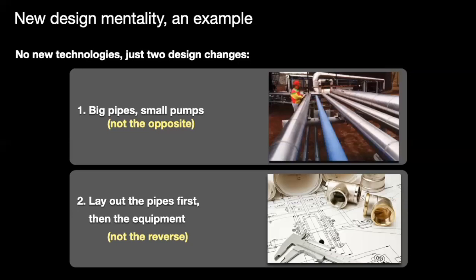But by then, A and B are far apart. Other stuff got in between. They're at the wrong height. They face the wrong way. And by the time the pipe snakes its way across the space, all neatly dressed at right angles like they teach us in trade school, it has about 3 to 6 times the friction that it would have had with a straight shot.